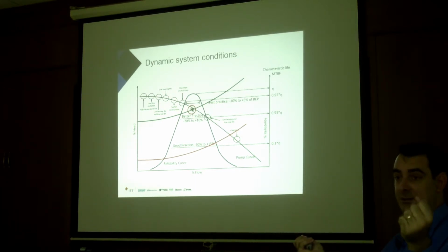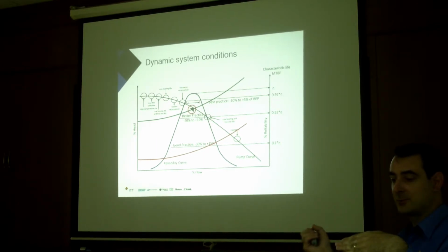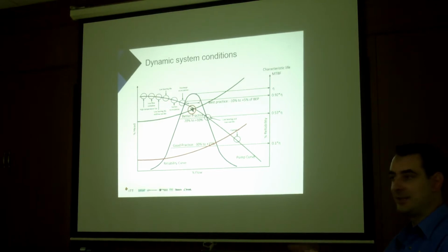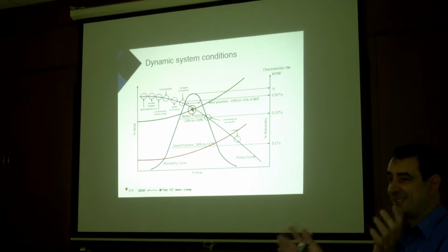They're going to use the feedback of the best efficiency point, throttle a valve manually, and then leave it. And then the Pump Smart will do the rest. Increase speed, decrease speed, because we'll always give them the same flow. That's the goal: constant flow. So yeah, for your application, you just ask me and I can help. I'll tell you what I need. Maybe I need the data sheet, maybe a P&ID.